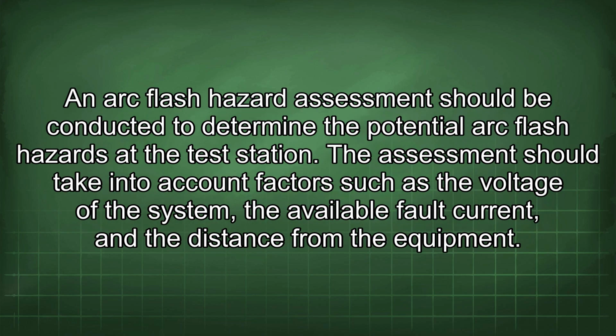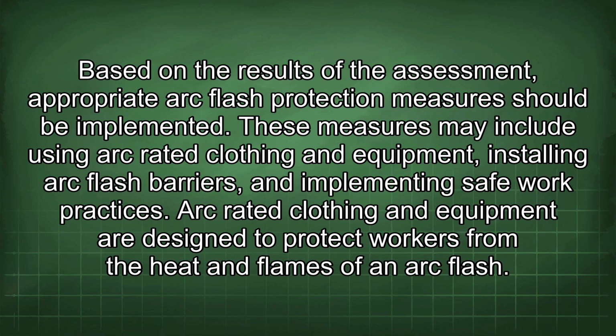An arc flash hazard assessment should be conducted to determine the potential arc flash hazards at the test station. The assessment should take into account factors such as the voltage of the system, the available fault current, and the distance from the equipment. Based on the results of the assessment, appropriate arc flash protection measures should be implemented. These measures may include using arc-rated clothing and equipment, installing arc flash barriers, and implementing safe work practices.